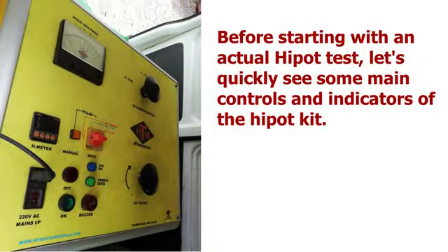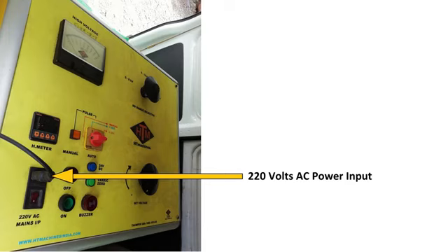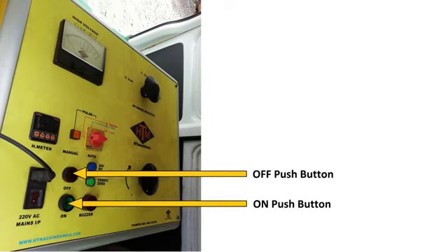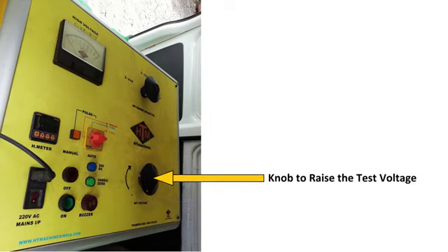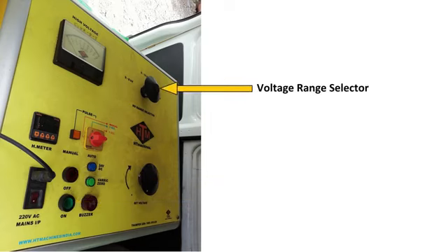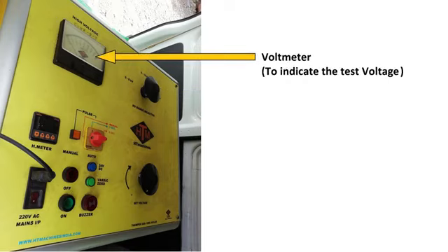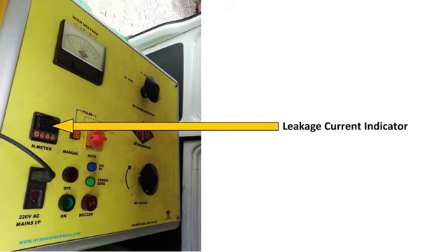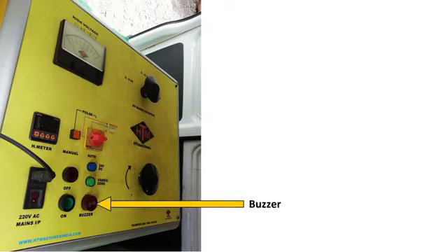Before starting with an actual hipot test, let's quickly see some main controls and indicators of the hipot kit. This is the 220 volts AC power input to the kit. These are on and off push buttons. This is the knob to raise the test voltage gradually. This is a voltage range selector. This is the voltmeter to indicate the test voltage, and this is the leakage current indicator. These are indicators and this is the buzzer.